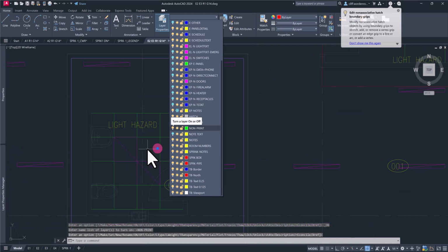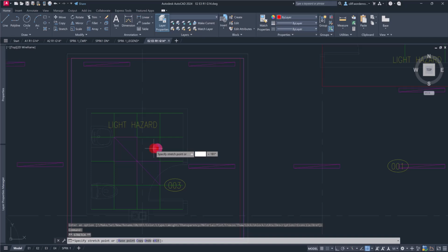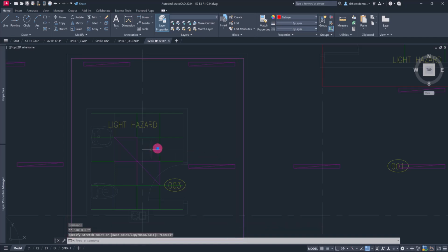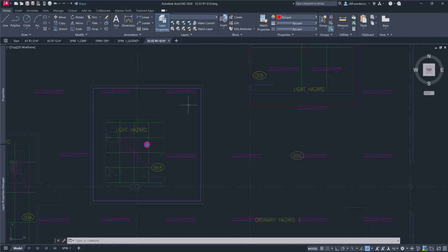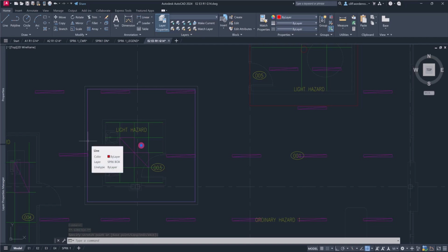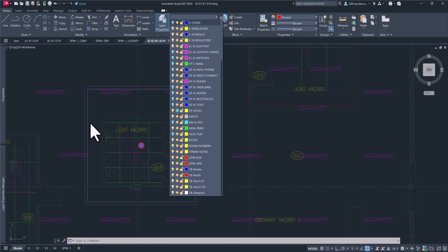If I have a T-bar, I don't want to put the sprinkler on the edge of where a T-bar is. What I want to make sure is that it is in the center of, say, this 2 foot by 2 foot tile. Now, what's nice here is this box has plenty of coverage, so I can move this around. If I move this pretty much dead center, that's what I'm looking for. And again, I've got lots of space here to cover it. So this only needs one sprinkler to cover that.